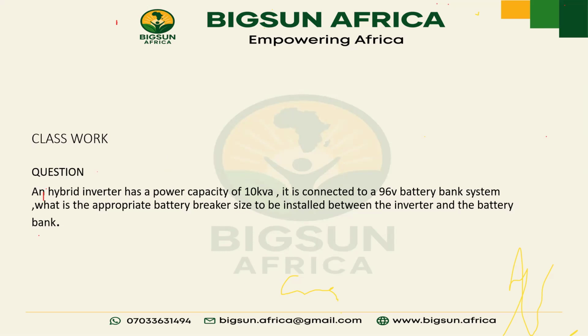our 10 kVA, which is the power capacity, multiplied by 1.25, divided by our battery, which is 96 volts. Let me press my calculator.